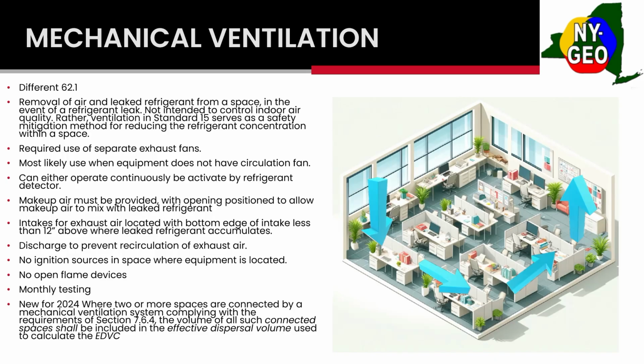And this is pretty common: the discharge must prevent recirculation of exhaust air. I know we've all been to sites where the exhaust and the supply air are right next to each other. We're not talking fumes anymore or grease. This is refrigerant. So we need to make sure that those are designed and installed correctly. And again, for flammable refrigerants, no ignition sources, no open flames, and monthly testing.